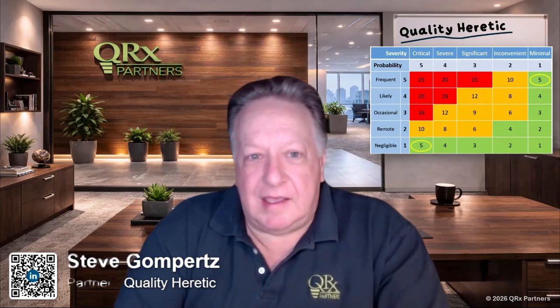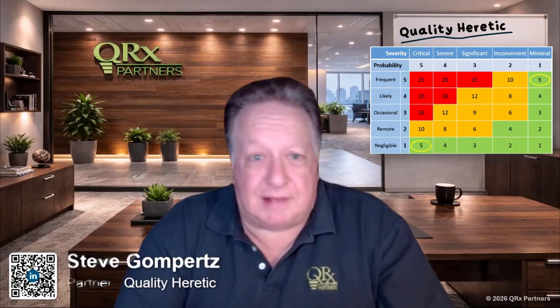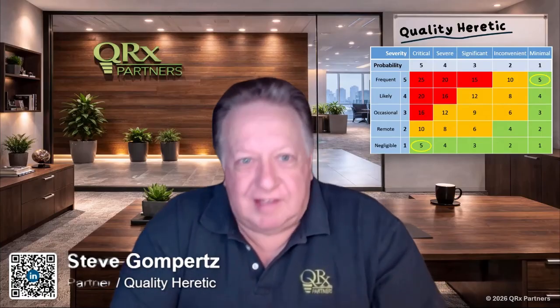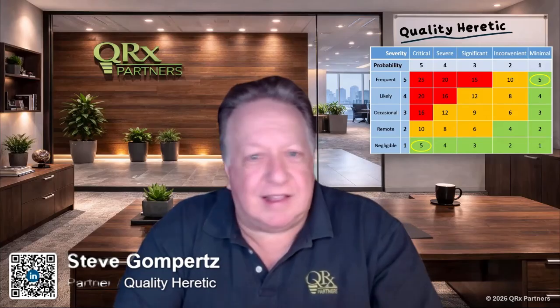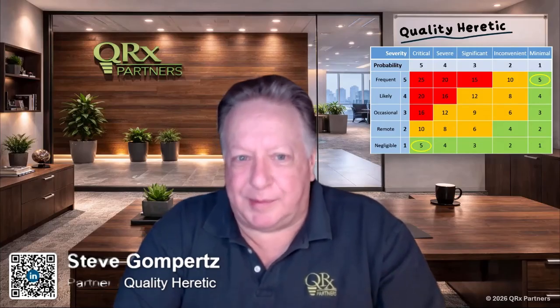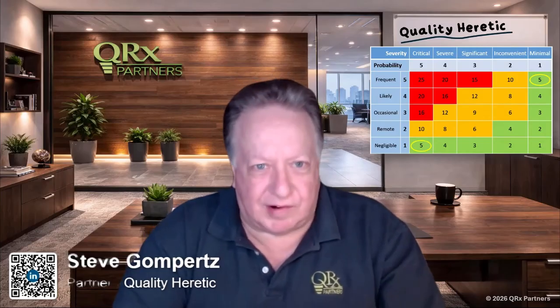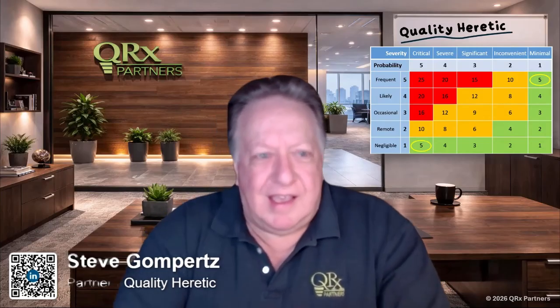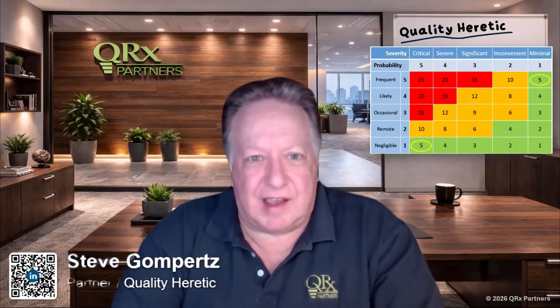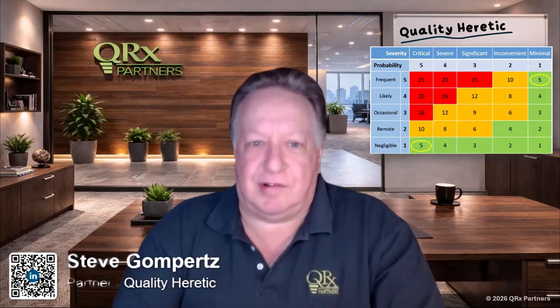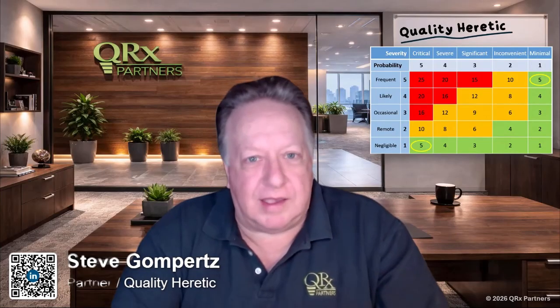Are they the same? Is something that's critical, and critical in the medtech space is usually reserved for death as the result, and it's negligible, but it's not zero probability? It's a non-zero probability of death. And then the other corner, upper right, it's something that happens a lot, but it has minimal impact, minimal severity. Are those really the same? I don't know that I would consider that. The fact that there's a chance of death, even though it's very small, that's not the same as something annoying that happens a lot to me. That's kind of how I look at it. So I think that's a fundamental flaw in our scales.